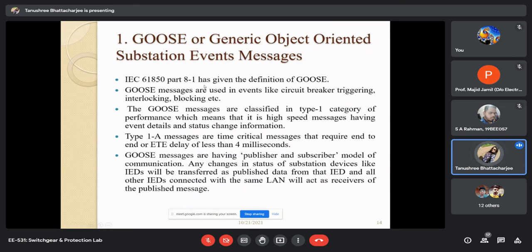So now coming to the first type of messaging, which is GOOSE, Generic Object Oriented Substation Events. What does it mean? The name itself tells us that whatever general events are happening to any object in the substation, that will be taken as an event and communicated between the IEDs. GOOSE communication makes the system smarter.